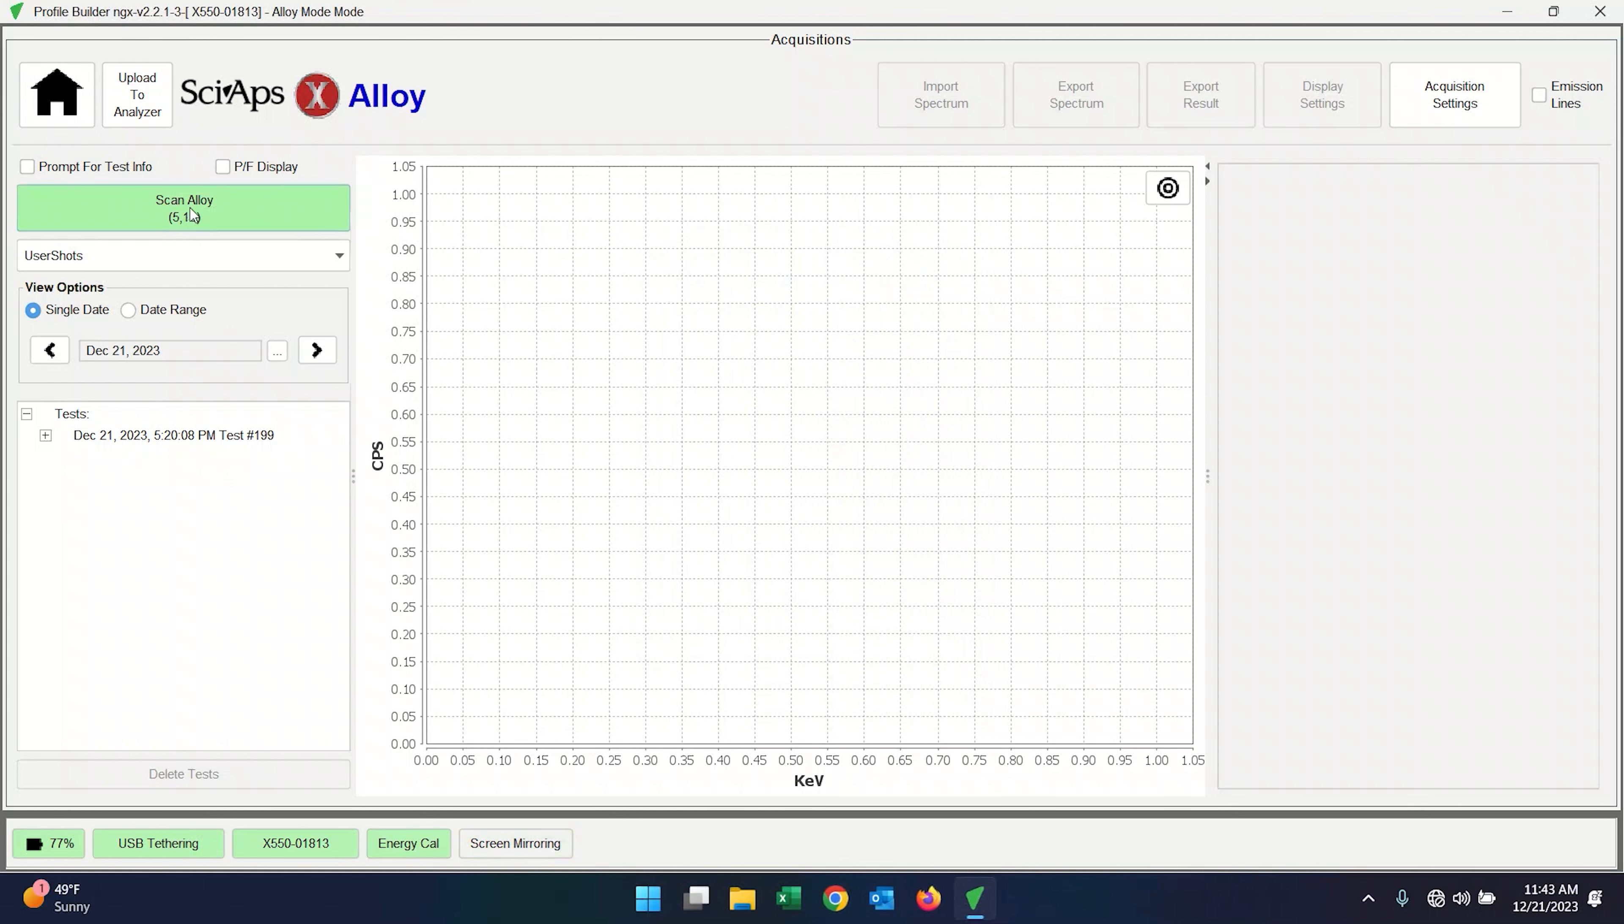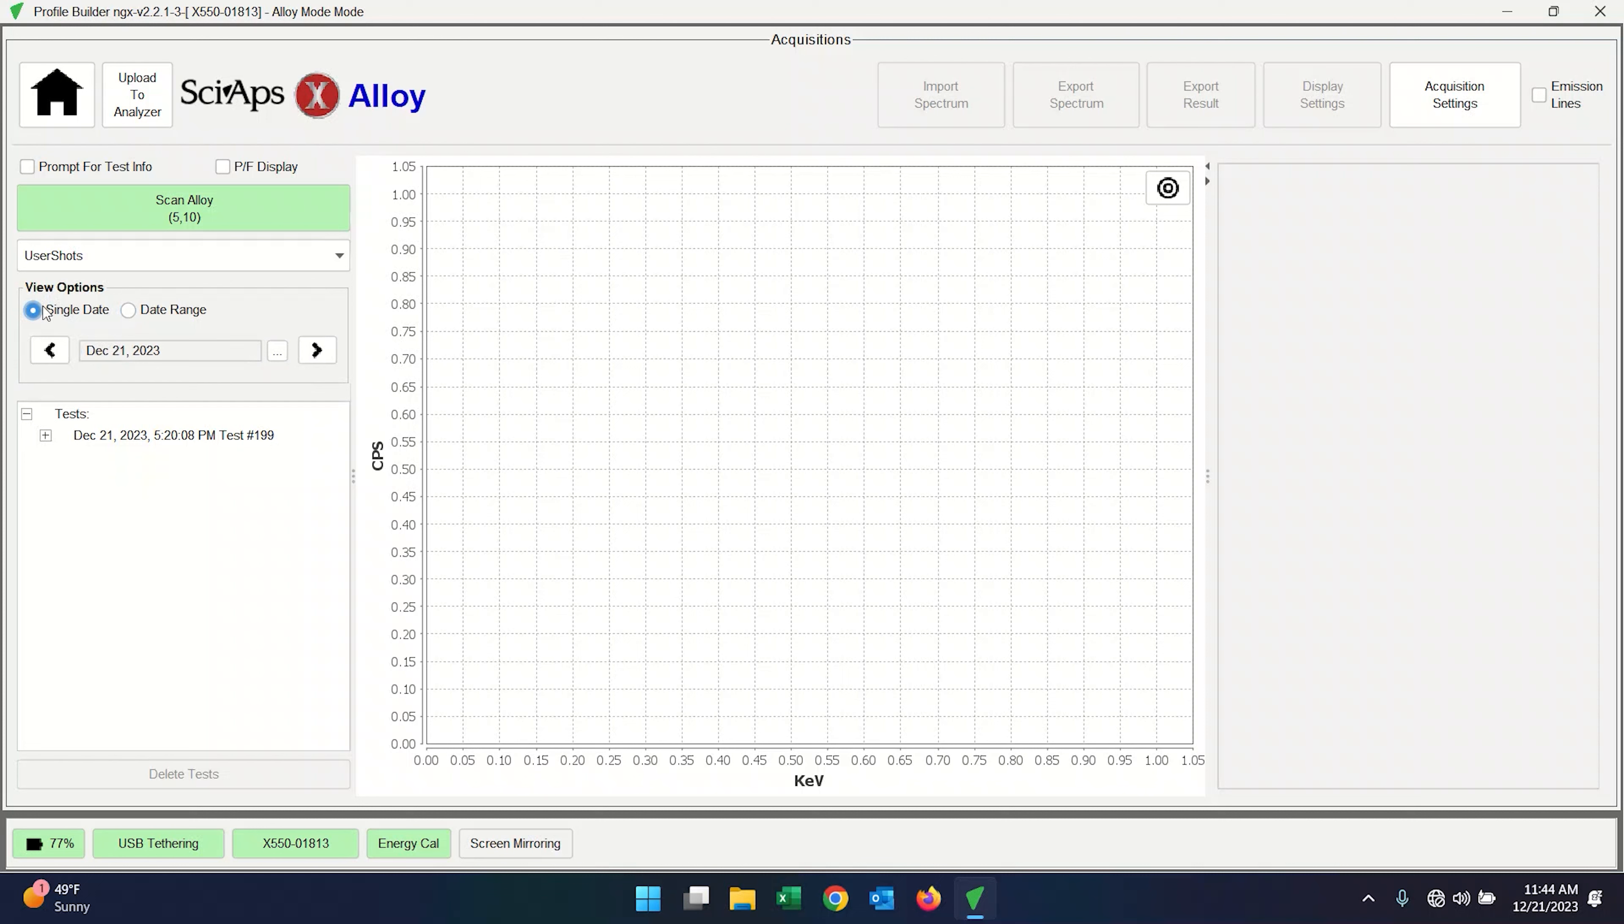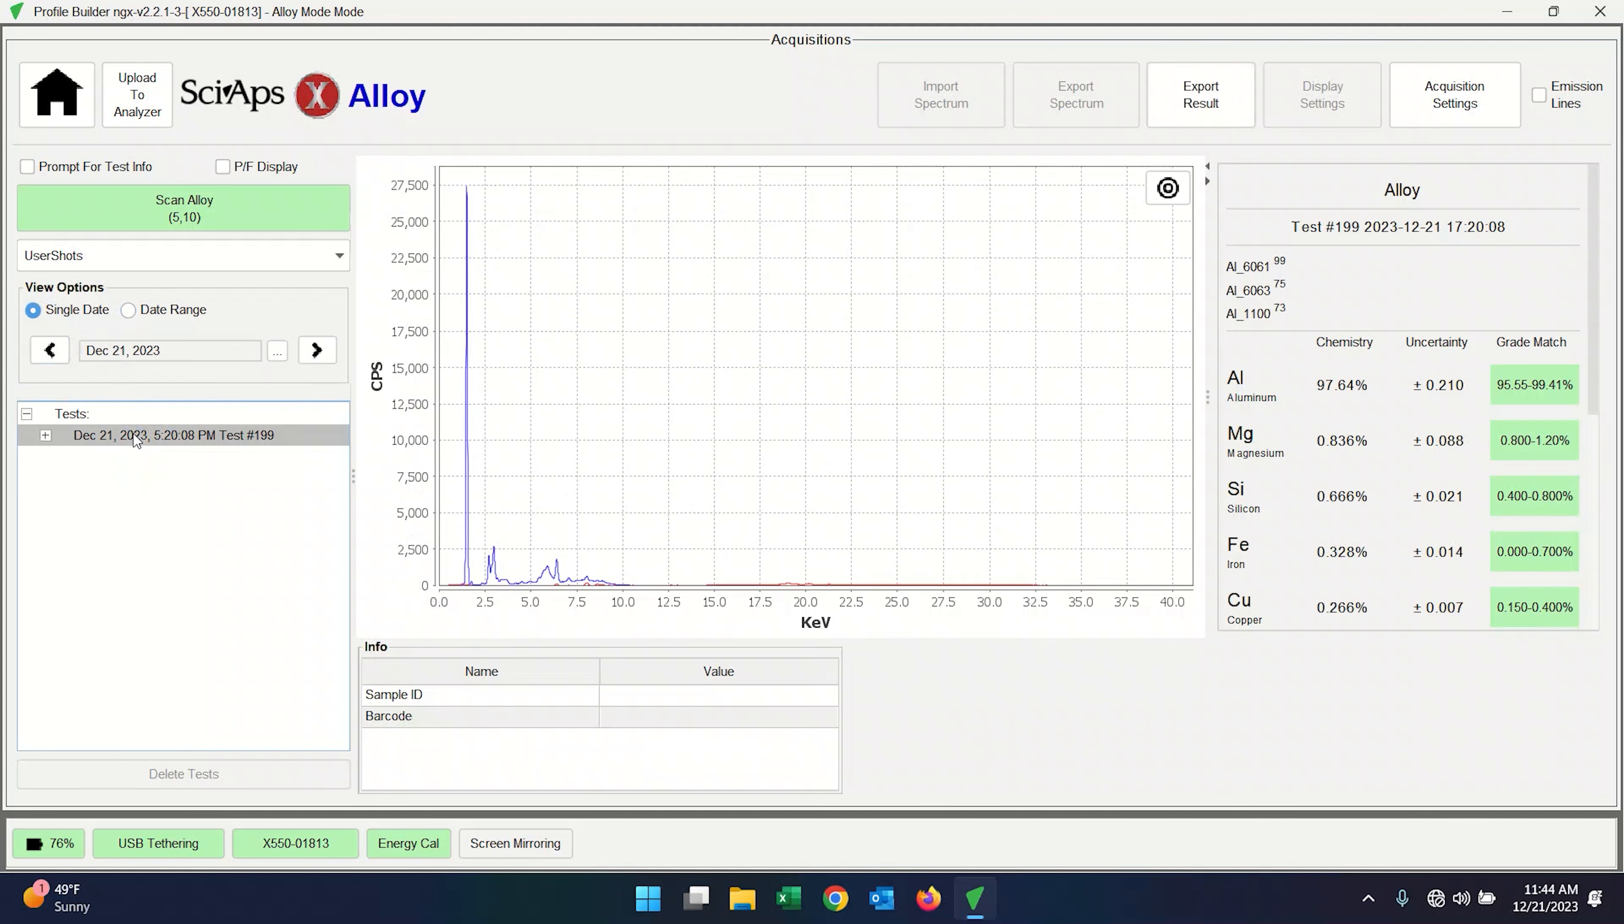So now we have the new window here. We're actually in the results. You'll notice if you hit this scan alloy button, that actually is showing you that it's going to do a five second heavy beam and a 10 second light element beam. It will fire the beam. You can run this remotely. So don't click that unless you're ready for it. And then down below, there's a date range you can select or a single date. Today is December 21st. So I'm going to do that one result, but a date range would be as simple as selecting the right date range for you.